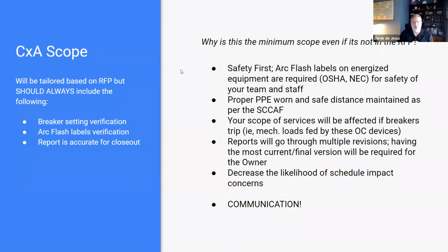As the commissioning agent, before you turn over a project, you should do a good breaker walkdown, we used to call it a breaker and valve walkdown. We'd walk down the mechanical system and check our valves to make sure they're in the right position, normally open, normally closed, and do the same with our breakers, checking which are open and closed and whether settings are correct. We even put tamper tape over the plastic window so those settings couldn't be changed.